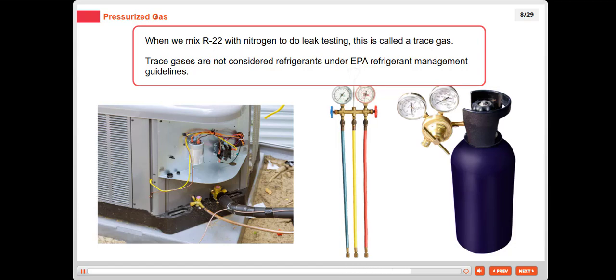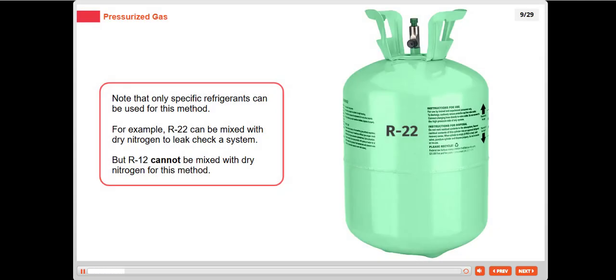Note that only specific refrigerants can be used for this method. For example, R22 can be mixed with dry nitrogen to leak check a system, but R12 cannot be mixed with dry nitrogen for this method.